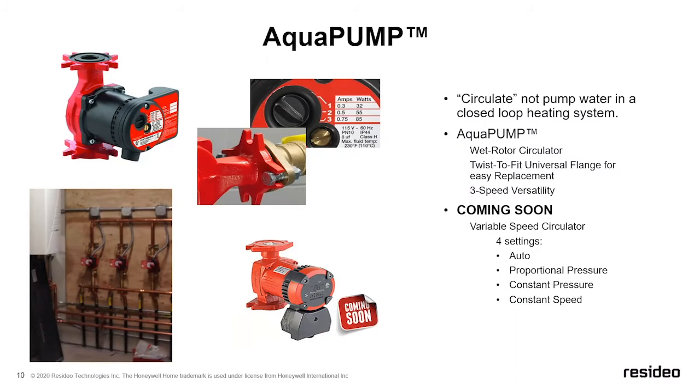And then every one of our 3 models is also a 3-speed circulator. So what that means is these are essentially fixed speed pumps, but it's almost like having 3 pumps in one. You can switch between 1, 2, and 3, as shown in the image, and it will actually change the pump curve and the energy consumption of that circulator. So it'll make it run faster or slower based on where you put the setting. And you'll notice it's also, as a result, going to draw more wattage depending on the pump, because you're basically making it a smaller or a larger pump.